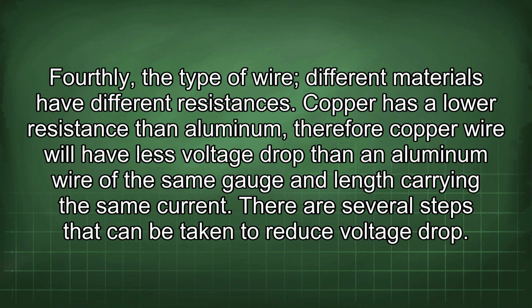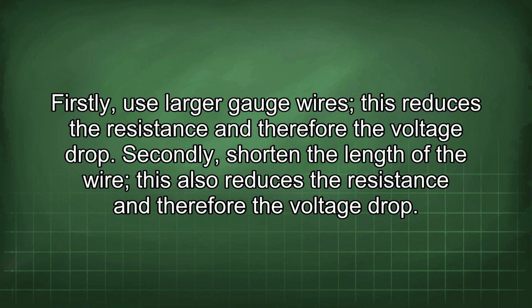Fourthly, the type of wire. Different materials have different resistances. Copper has a lower resistance than aluminum, therefore copper wire will have less voltage drop than an aluminum wire of the same gauge and length carrying the same current. There are several steps that can be taken to reduce voltage drop. Firstly, use larger gauge wires. This reduces the resistance and therefore the voltage drop.